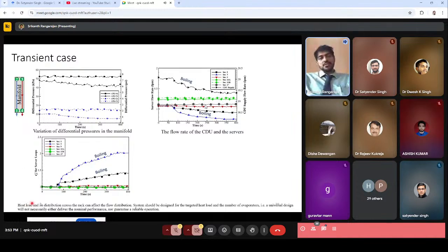So the heat load and its distribution across the rack can affect the flow distribution. The system should be designed for the targeted heat load and the number of evaporators. A universal design will not necessarily deliver nominal performance nor guarantee reliable operation.